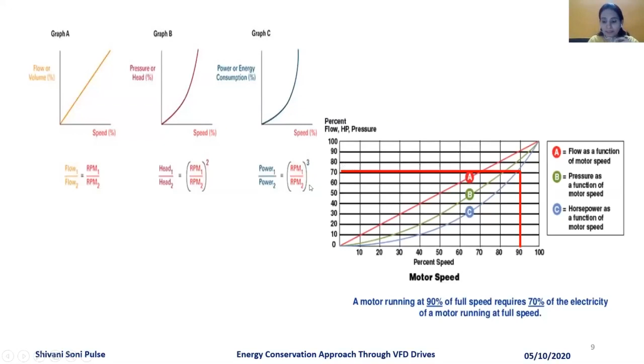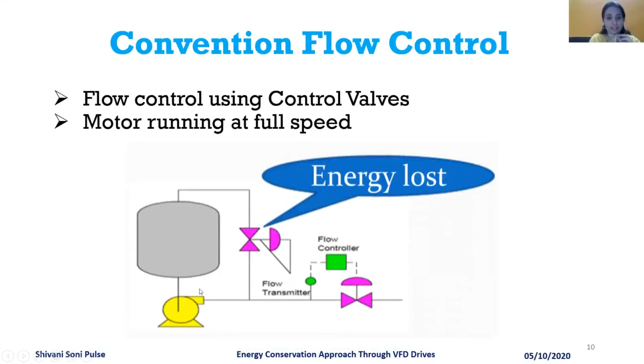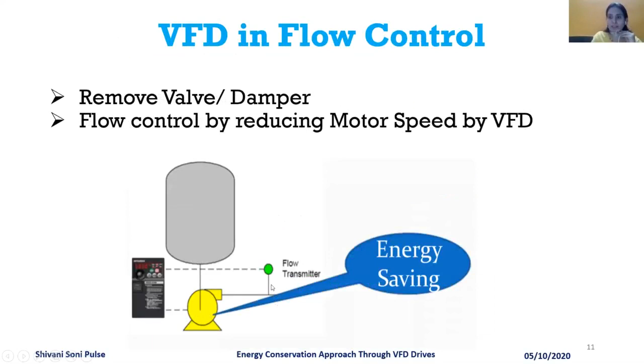Now see here that in the conventional flow method, we generally use flow control valves. In those control valves there are a number of losses, energy losses, and mechanical and electrical losses that affect the systems. Instead of this conventional method, if we use the VFD, we just remove the control valve, and the pump or fan is controlled by the VFD motor, so we save energy as per the power consumption.